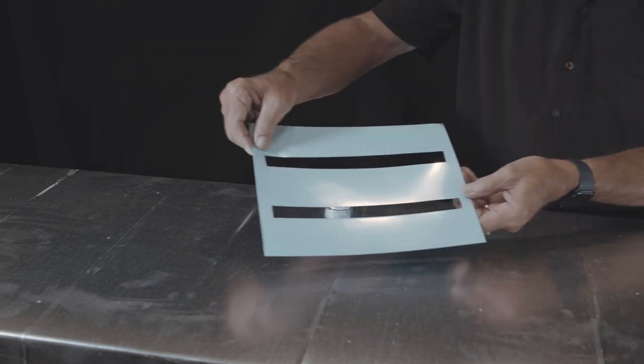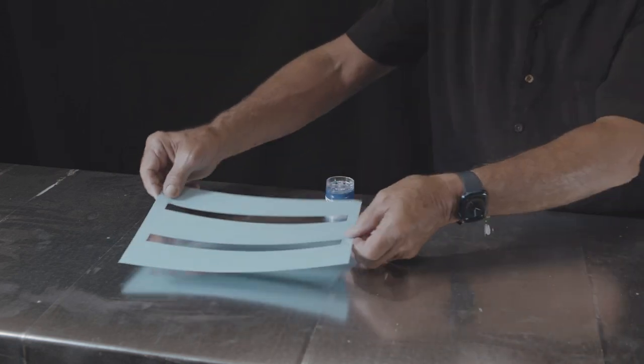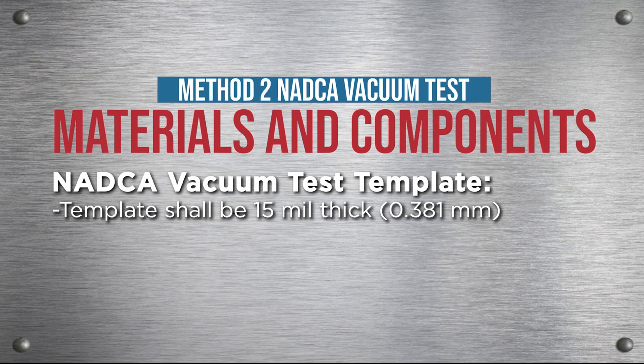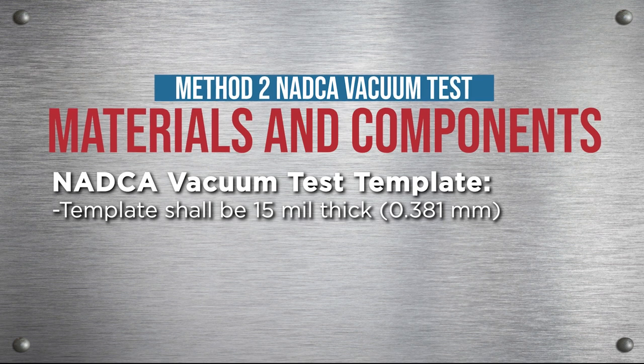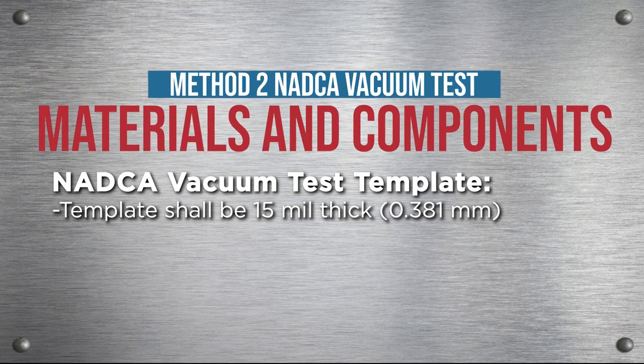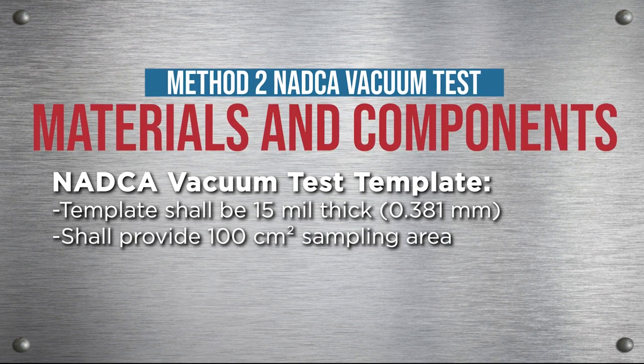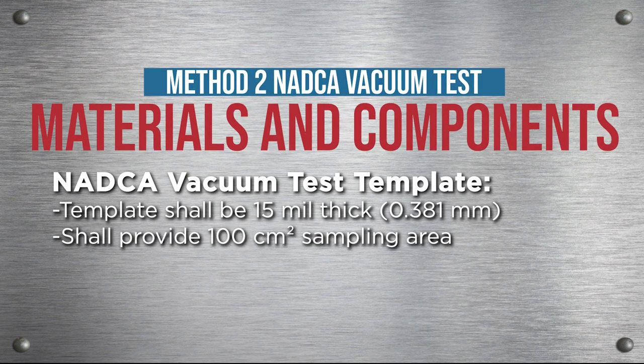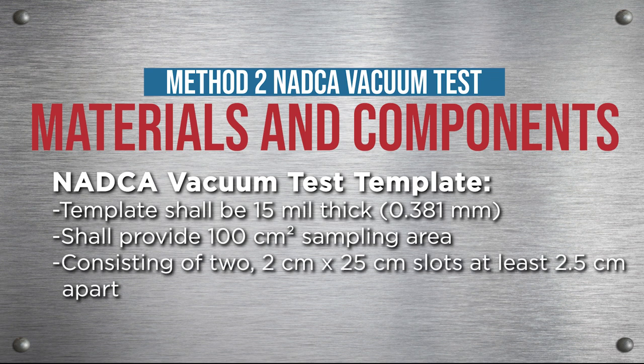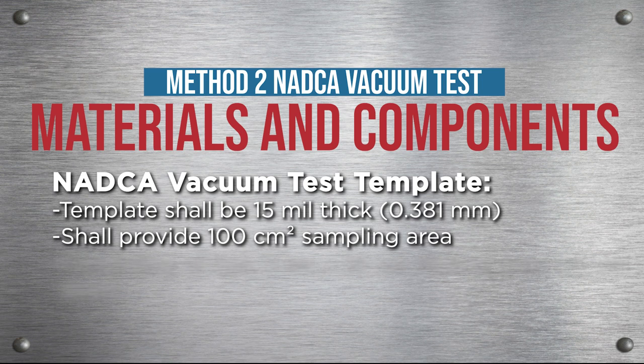NADCA vacuum test template: the template shall be 15 mil thick, 0.381 millimeters, and shall provide a 100 centimeter squared sampling area consisting of two 2 centimeter by 25 centimeter slots at least 2.5 centimeters apart.